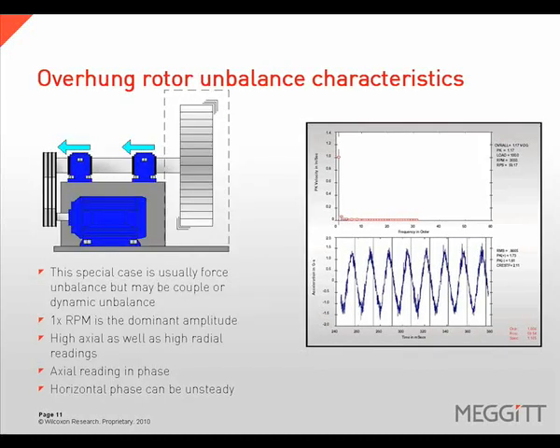Overhung fans exhibit special vibration characteristics. High axial 1 times readings as well as high radial 1 times readings are common on both bearings. The axial phase readings should be in phase, while the horizontal phase readings can be unsteady.